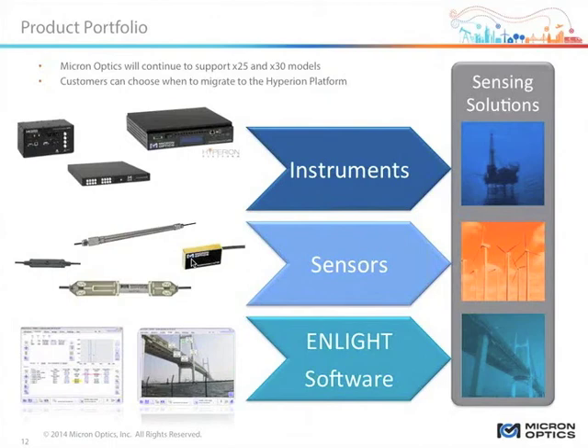So the short answer is that we will be handling that in a very similar way that we've done the SM130, which is by knowing the distance. That distance is really an optical path length. It's really the time of flight that is of concern, and so by knowing what that time of flight is, by knowing the refractive index paired with the physical distance of fiber, we can take that measure into account when we calculate the wavelength.